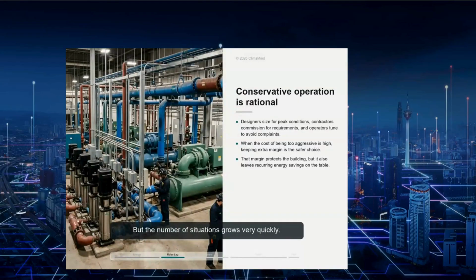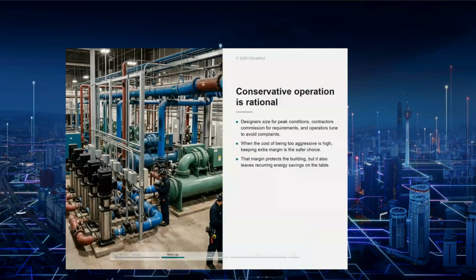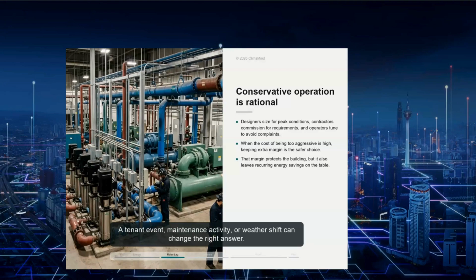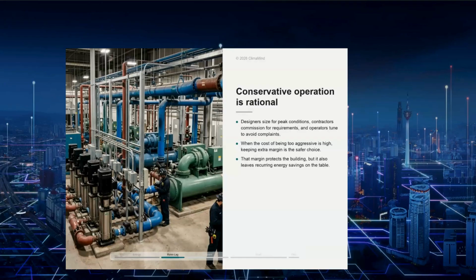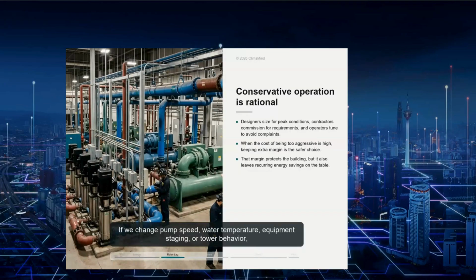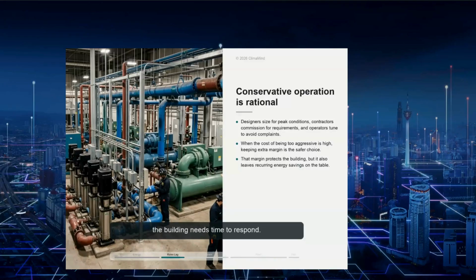But the number of situations grows very quickly. Morning is different from afternoon. Humid days are different from dry days. A tenant event, maintenance activity, or weather shift can change the right answer. And HVAC decisions do not show their full effect immediately. If we change pump speed, water temperature, equipment staging, or tower behavior, the building needs time to respond. So the question is not only what should we do now? The question is, if we do this now, what will happen over the next few minutes or the next hour?